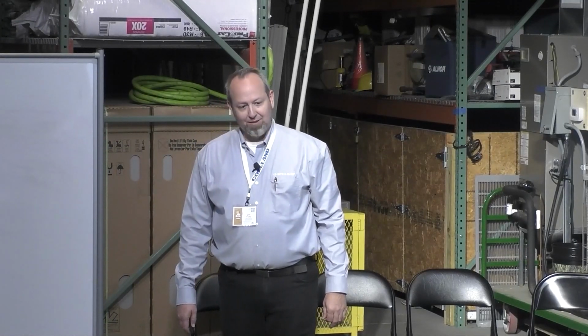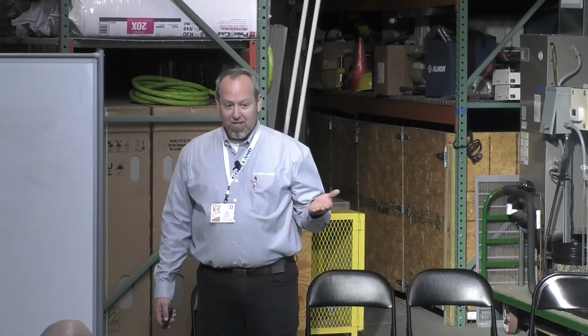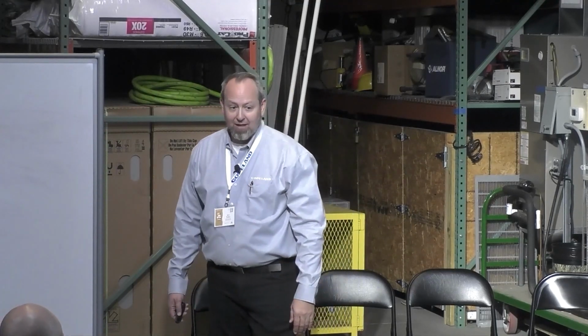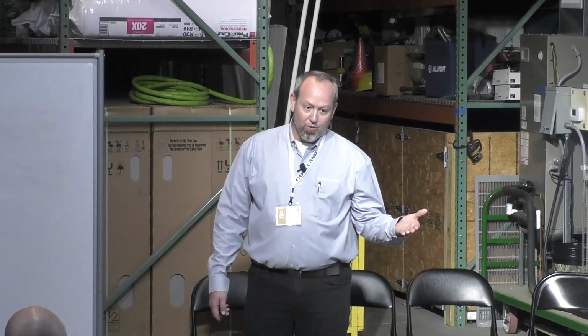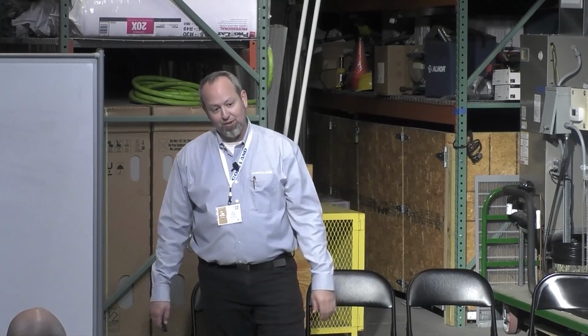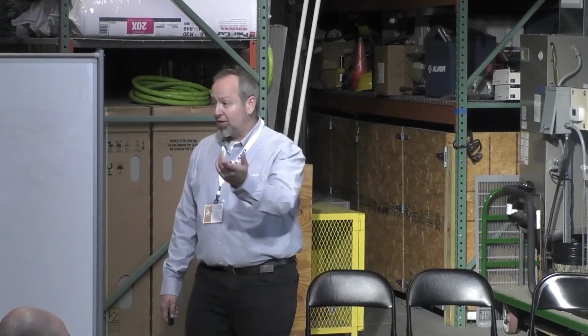There isn't. As far as the load, you want to be wherever your manufacturer installation instructions tell you to be. And there again, the slower you go, the less capacity you have. You're losing efficiency and capacity the slower you run your fan. That air has to go across that coil at design temperature to be able to pull the maximum efficiency off of it. So any other questions, come up and talk to me.